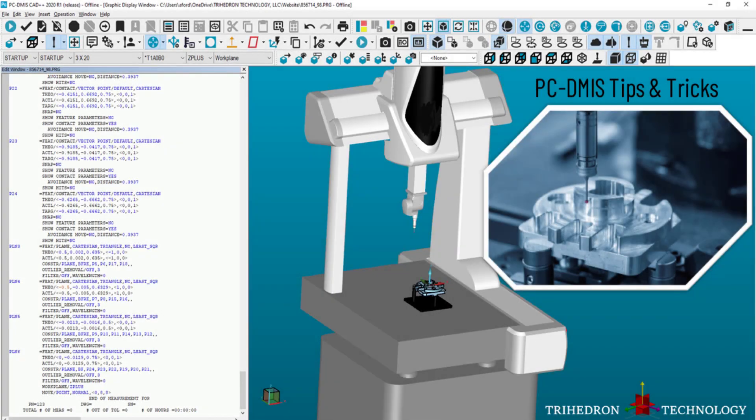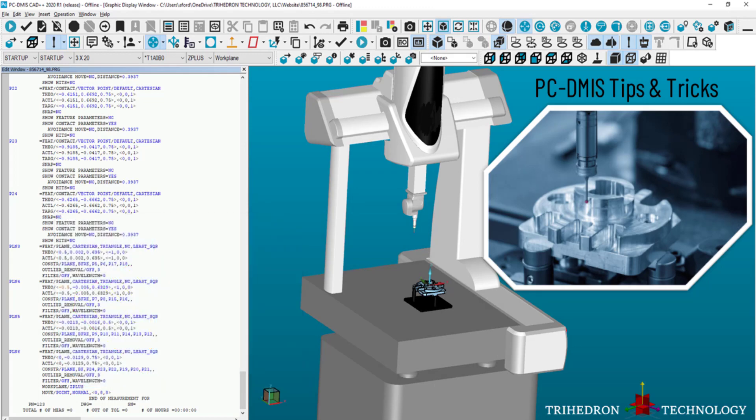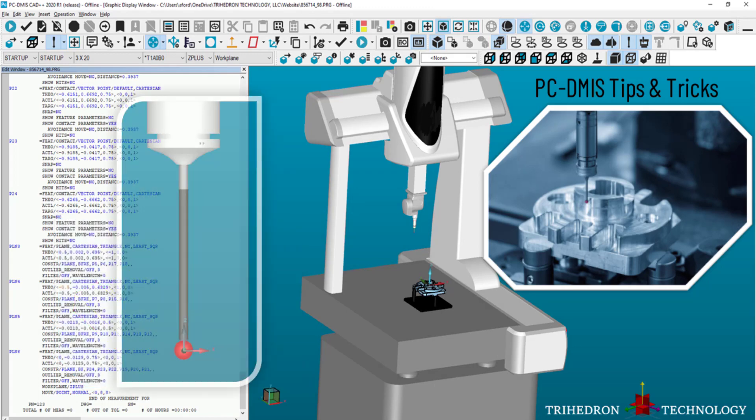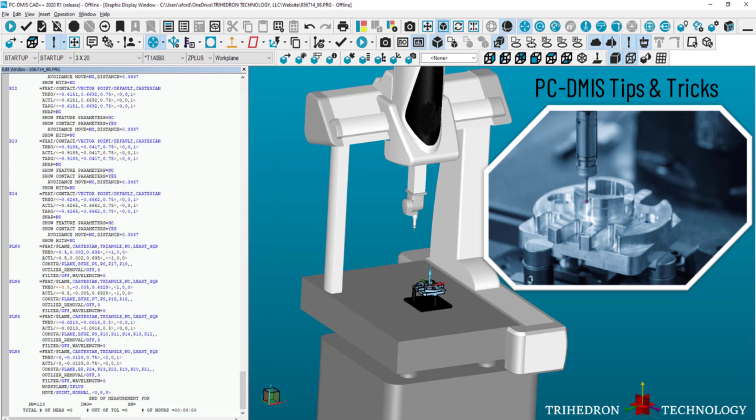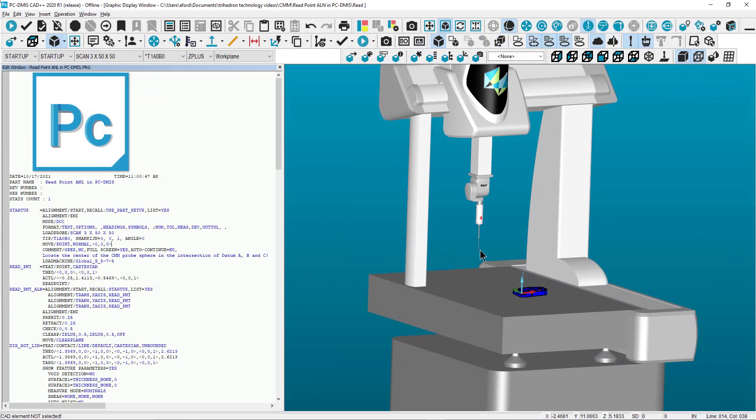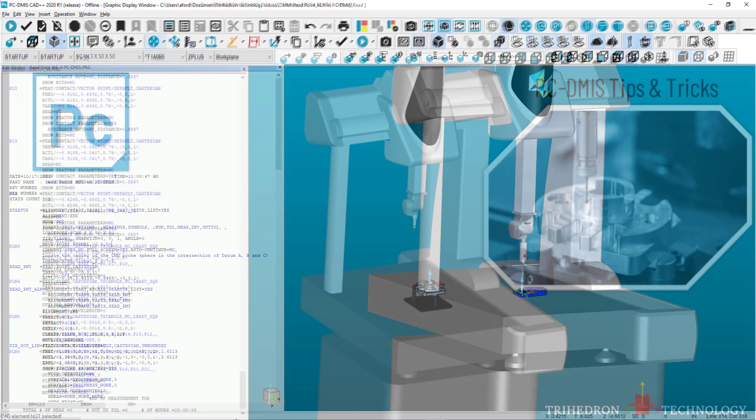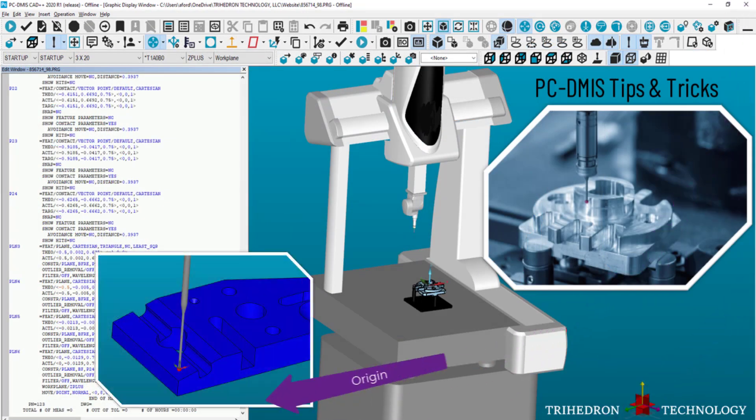This video will teach you how to effectively use a read point alignment in PCDMIS. The read point command records the physical location of the probe sphere center. This type of alignment allows the operator to manually position the probe in a desired place, aka the origin. This lets the CMM know the location of the workpiece without having to take a number of manual hits on the part.